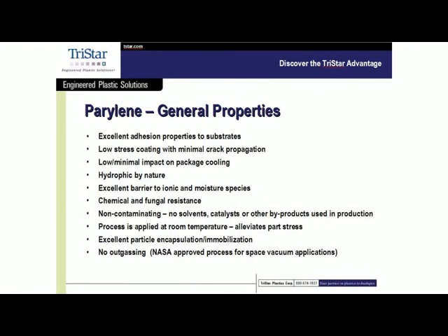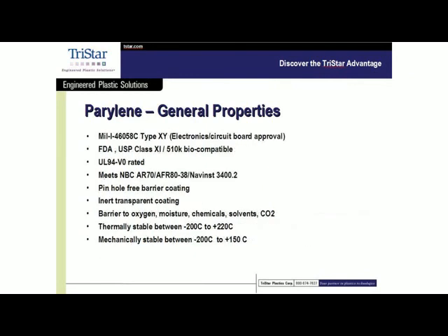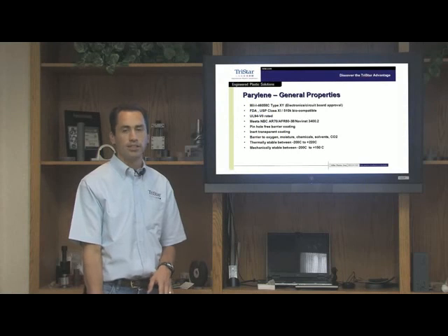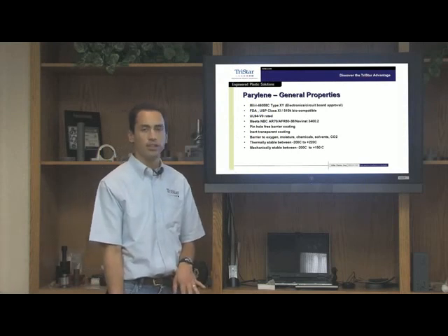It is pinhole free, hydrophobic, lubricious, and fully conformal. It has good temperature resistance, and it's USP class 6 and 510K compatible. So essentially, we can actually coat any material with parylene to make it implantable or completely inert and resistant to any solvents or environmental conditions.